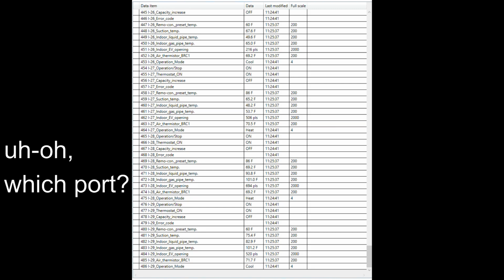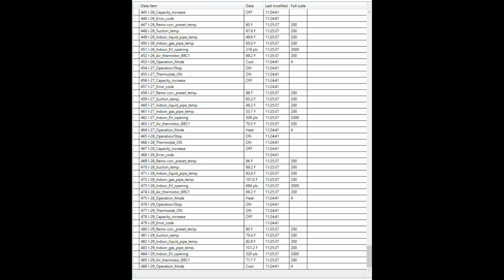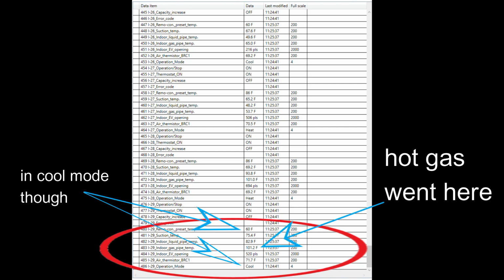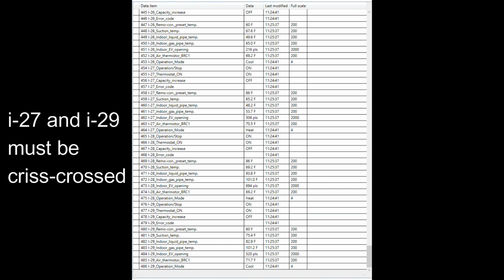So we need to look at all the other indoor units and see which indoor unit is calling for cooling, but is actually receiving that hot gas. And you don't have to look far in this particular case because I-29 is getting hot gas right now and it's in the cool mode. Here is where a lot of folks make the big mistake though. The first instinct is to think, oh, these two units must be crisscrossed. But if you were to assume this, you would very possibly be wrong.